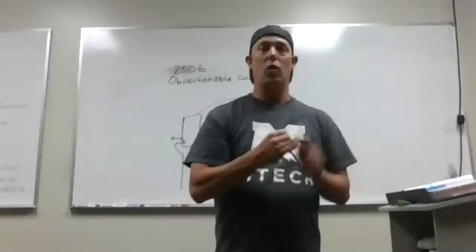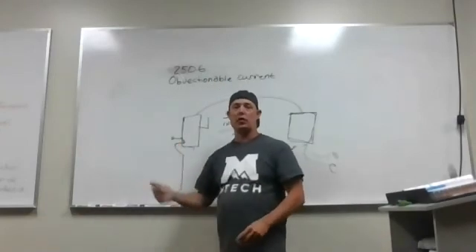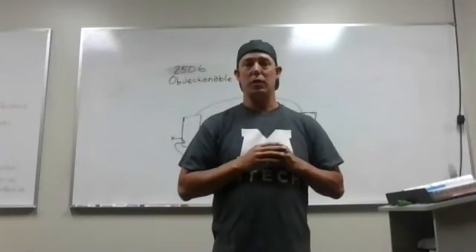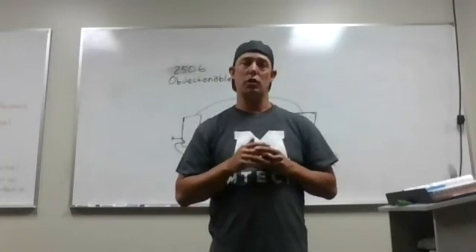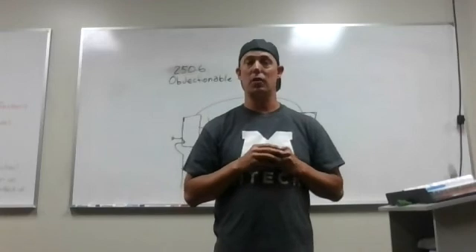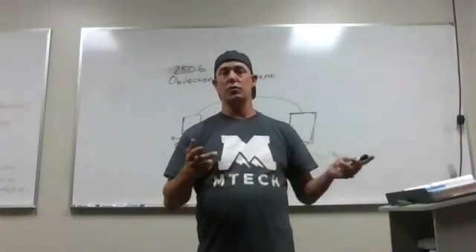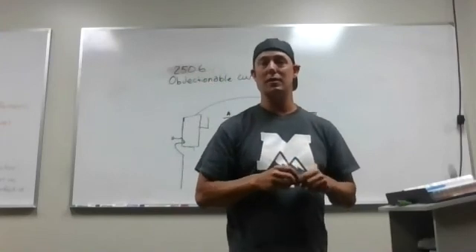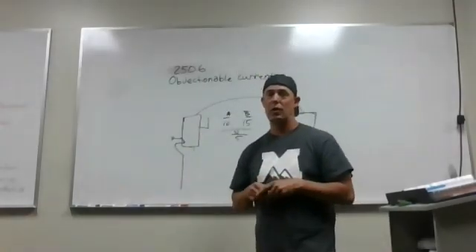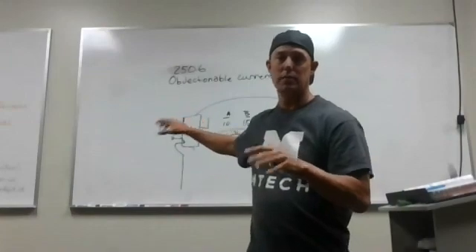I don't know if you're a handyman or a homeowner watching this, but if you bond anywhere beyond the main point of disconnect, you will have objectionable current and you could kill somebody. So please pay attention. Don't become a YouTube electrician and just wire up stuff without knowing what you're doing. This is a huge problem, and that's why our code says it has to be free from objectionable current. Thank you guys — hit me up on Utah Electrician on Instagram or this YouTube channel, or email me at cgermanelectric@gmail.com. I also do consulting and teach four nights a week at MTECH. I love this trade and I want to avoid this at all costs. Have a great day.